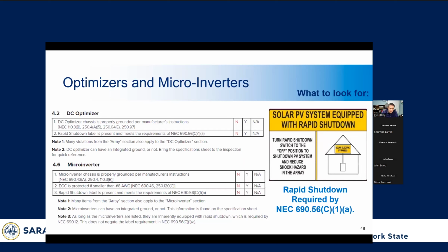So one way that DC optimizers and microinverters are similar is the rapid shutdown features. They both have them, and this is a method in the code where DC conductors are shut down at a level close to the array. If power is interrupted, the system shuts down to prevent live DC conductors in the system or the building. Using this feature that they have already installed is an allowable way within the code to provide rapid shutdown to the whole system. That's an important point. You don't have to have a separate rapid shutdown method if they already have it.